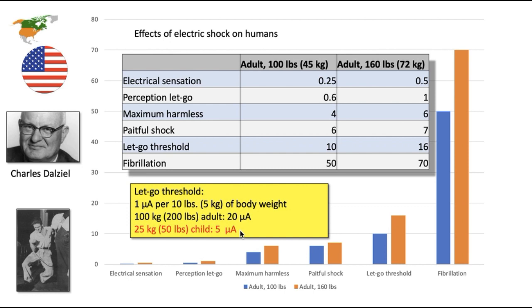Which also has another great consequence. If a child weighs, let's say, 15 kilos or 30 pounds, even a 5 milliamp GFCI or an RCD may not save that child.